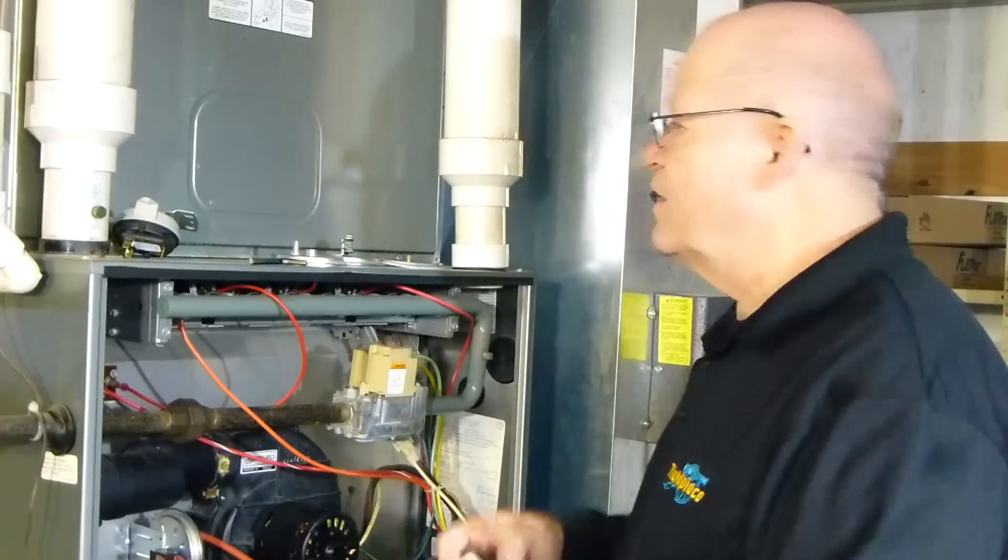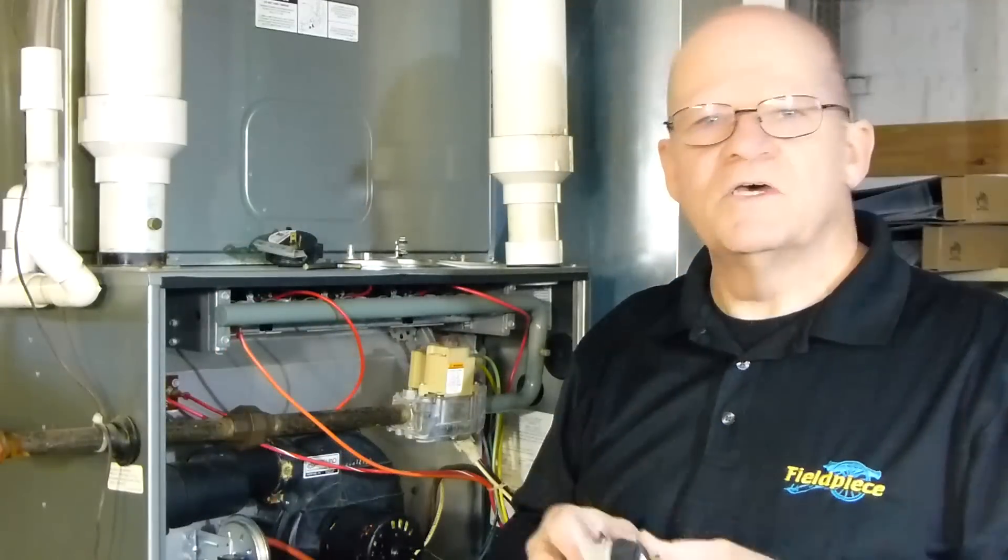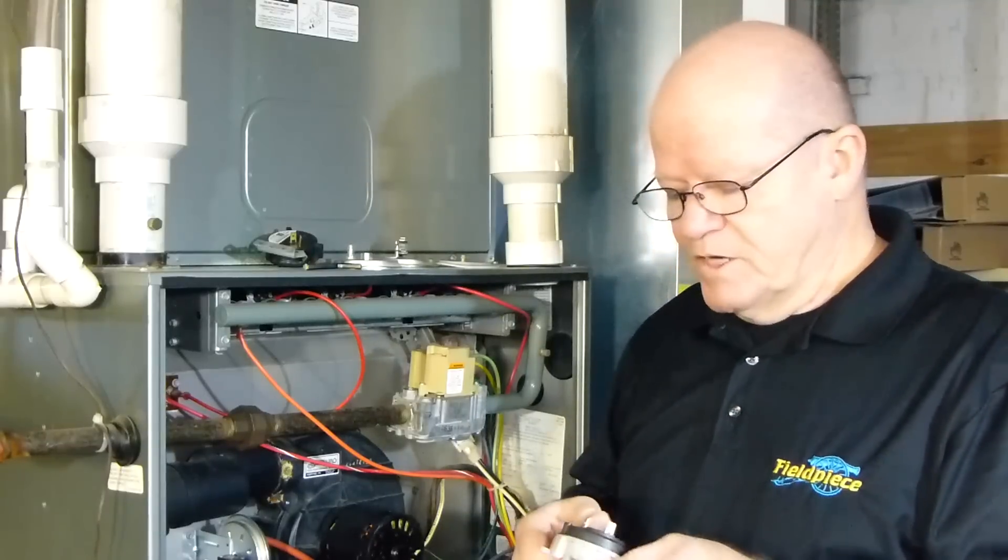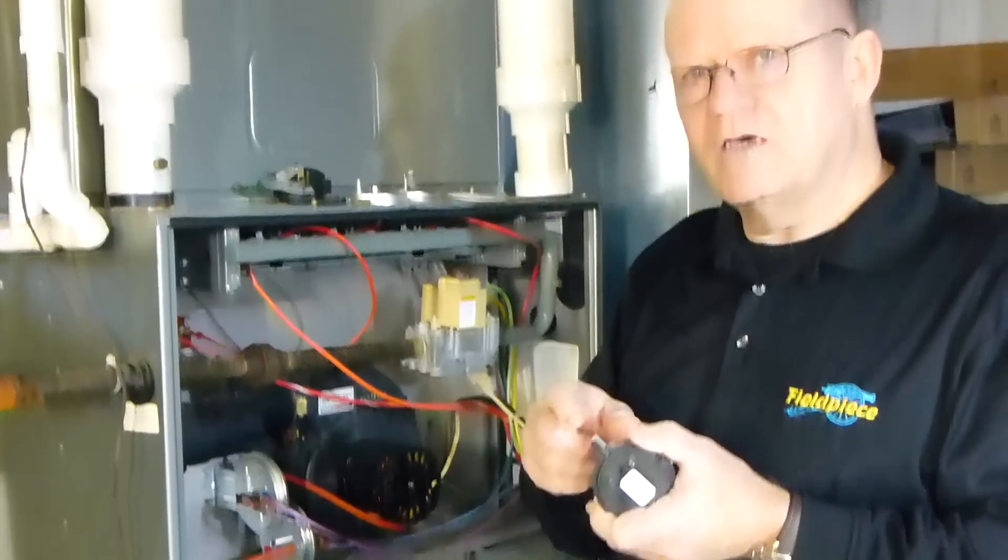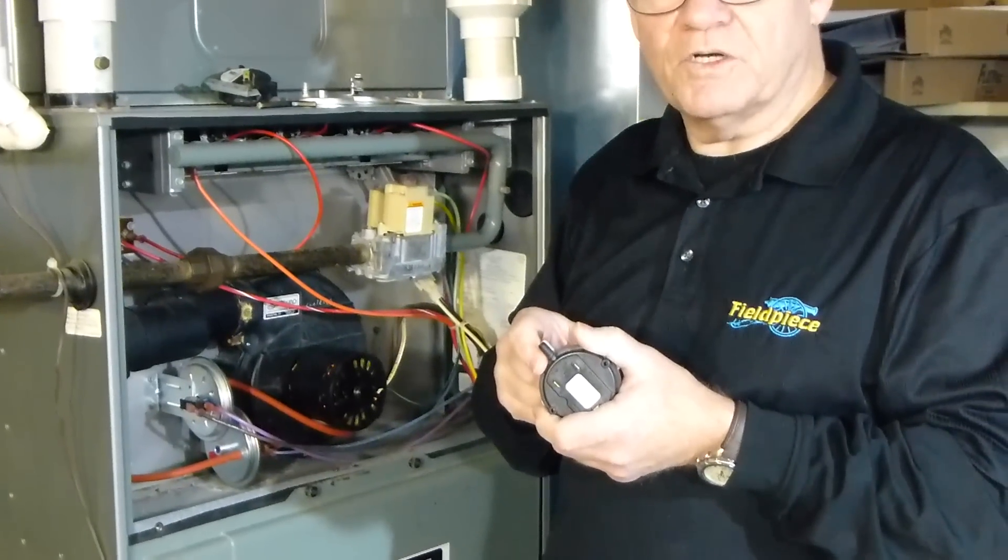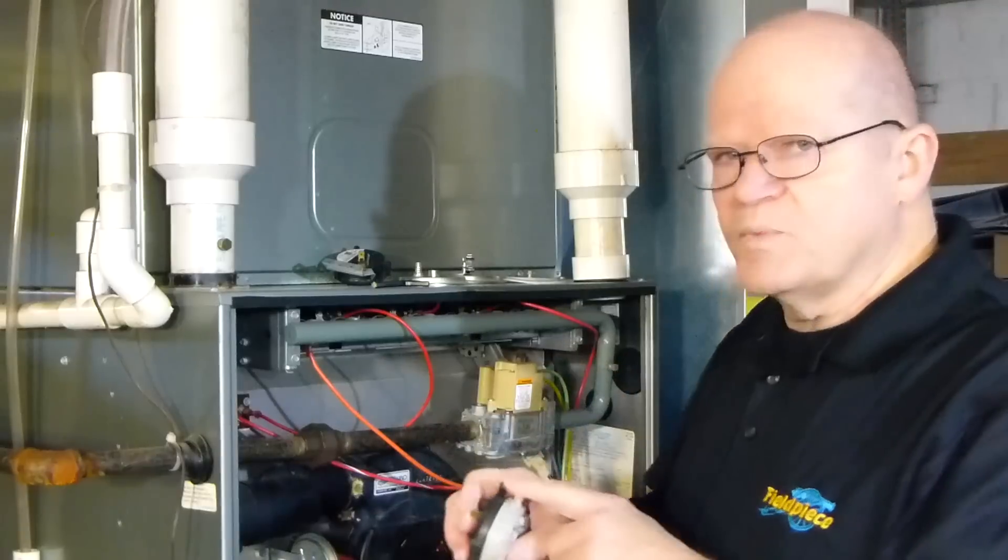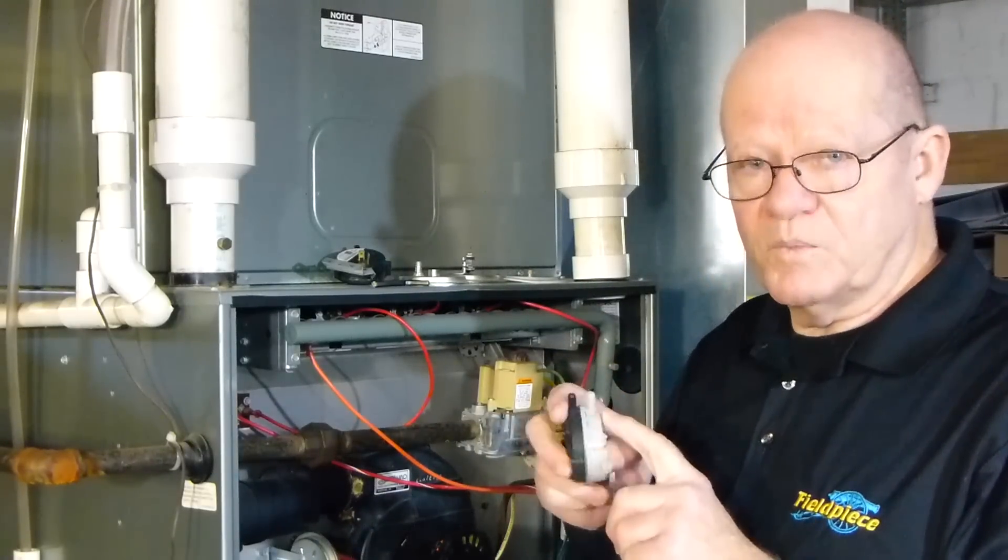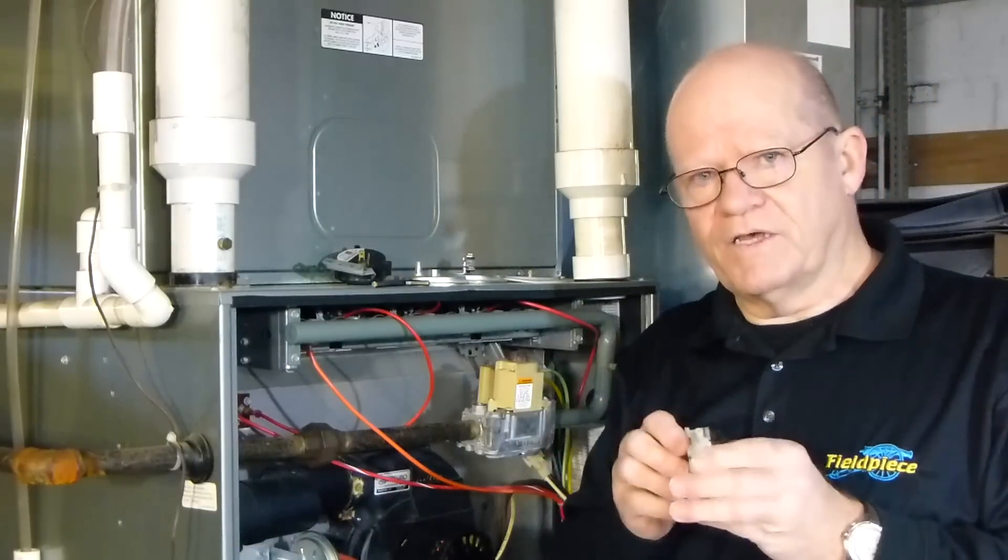The other thing is when you're going to go out into the field and you're going to purchase a calibrated adjustable pressure switch that you can calibrate, there are several different styles that are out there. This one is small, it has multiple footprints—basically multiple mounts—and you can do a dual pressure switch on it. Let's talk about dual pressure switches.